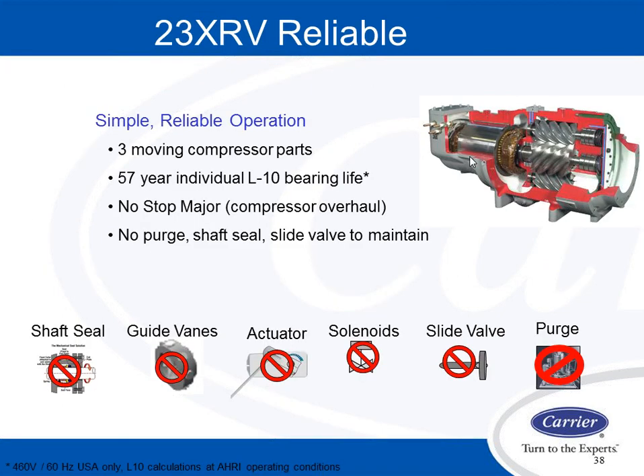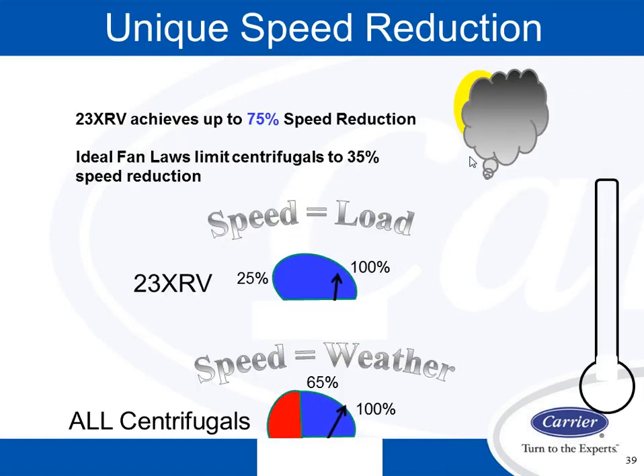Again, 3 moving parts, 57-year individual L-10 bearing life, no major compressor overhauls, no purge, no shaft seal, no slide valves. It's a fantastic machine for an end user who's going to look at the overall life cycle of a chiller.